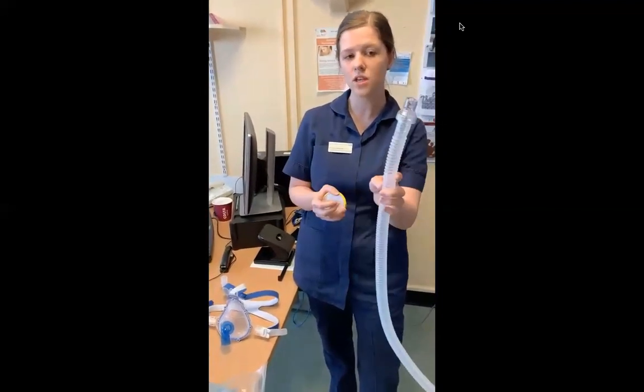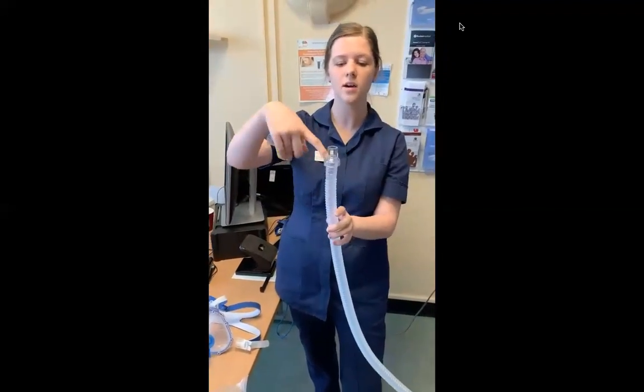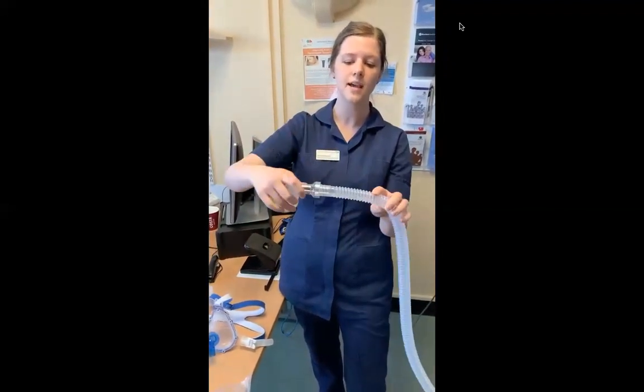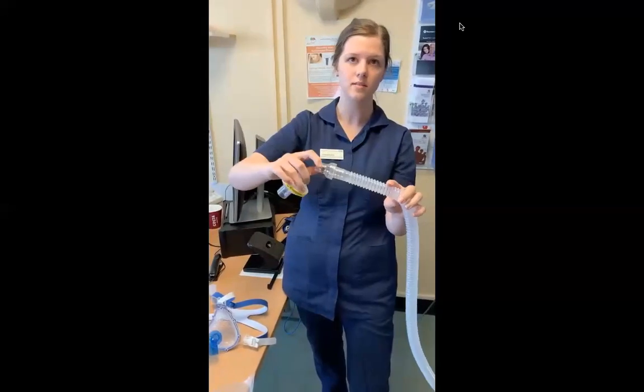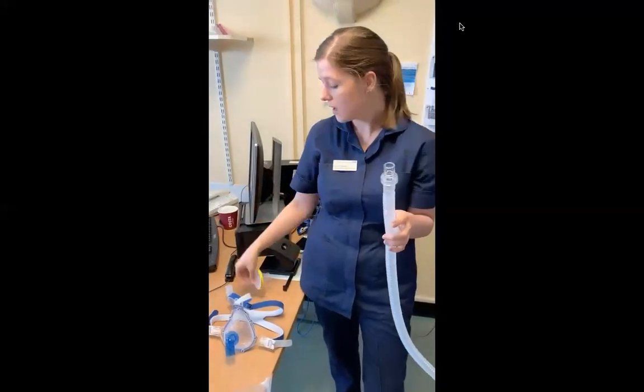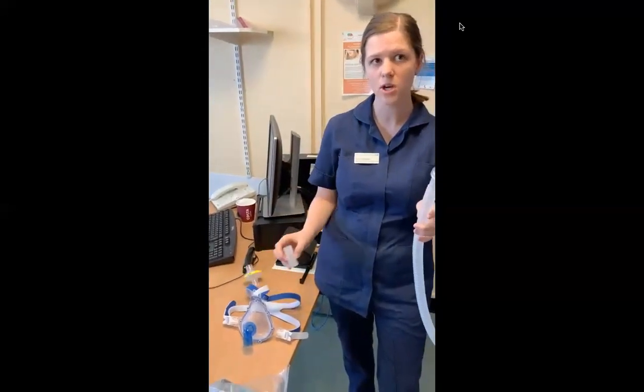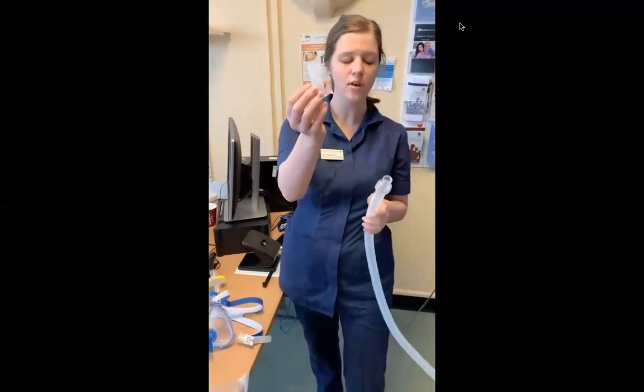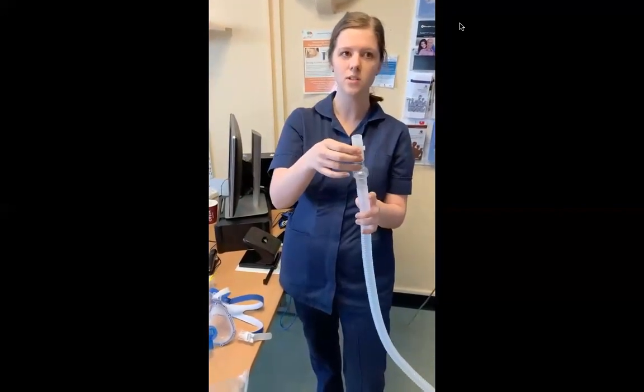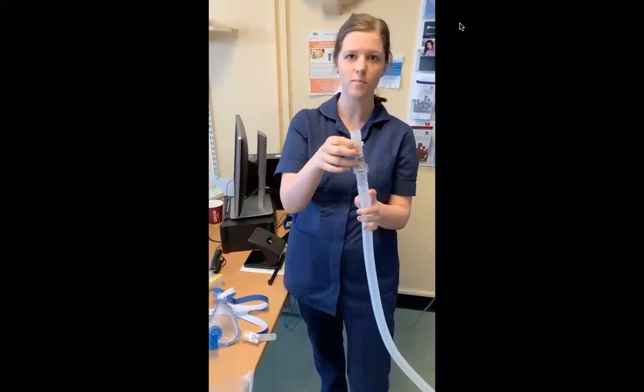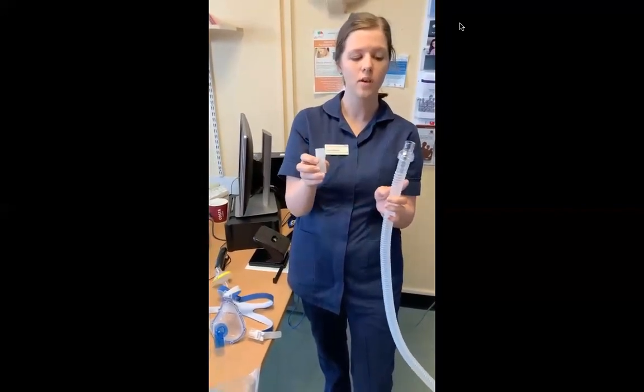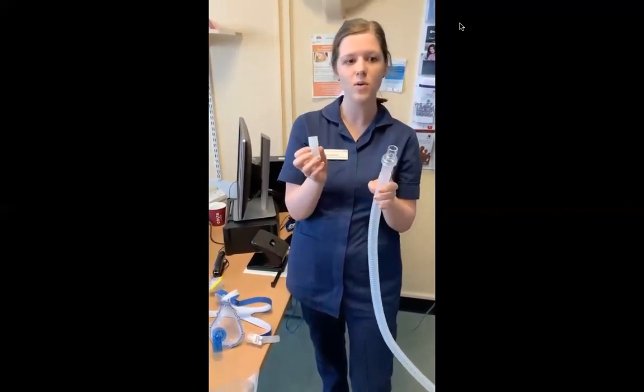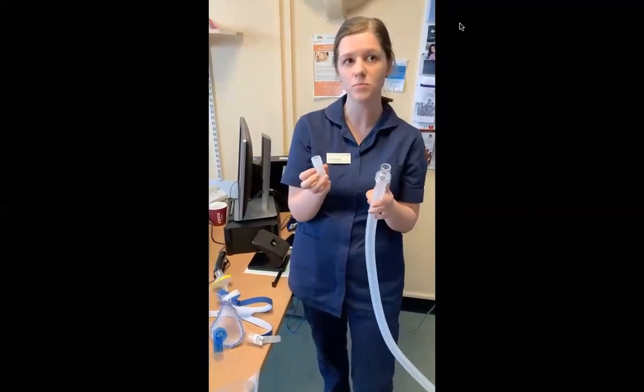If you're using Drager tubing, which you will know, there is a Drager at the top here, it says there is an exhalation valve inside the tubing, so you do not need to add one. If you're not using Drager tubing, because there's two types of tubes, you'll need to use this valve. The valve won't fit on the Drager tubing, so you know that you don't need it for this one. It will fit on the other tubing. You definitely need an exhalation valve, otherwise it's unsafe for the patient because they won't be able to breathe out.